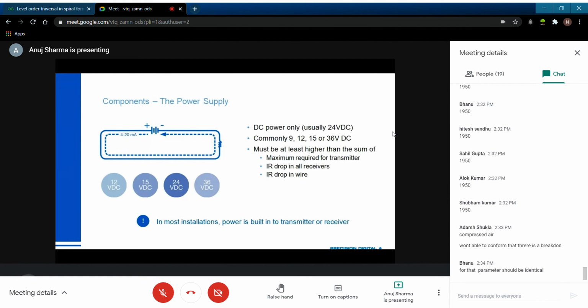There's 9, 12, 15, 36 volts. There's probably some other oddballs out there that you'll run into as well. But the idea here is that all they're doing is providing the DC voltage. They're not regulating the current. That's the job of the transmitter. The critical part about the power supply is that whatever voltage you're providing, it needs to be higher than the sum of the voltage drops in all the other elements of the loop.